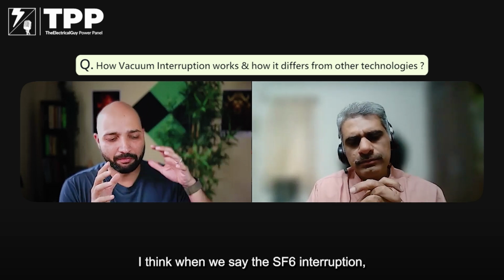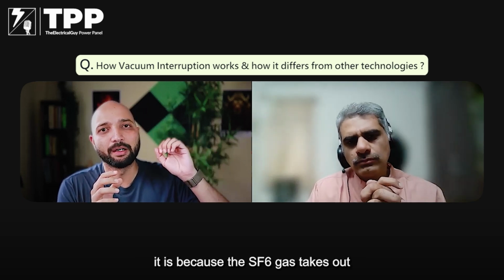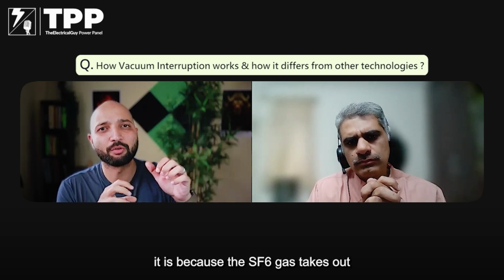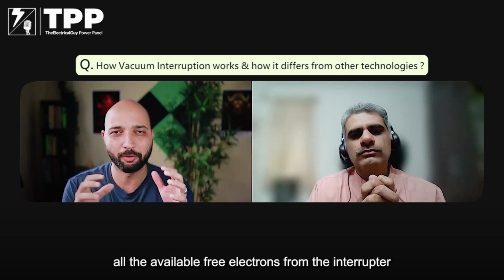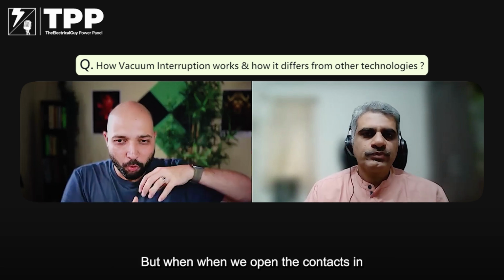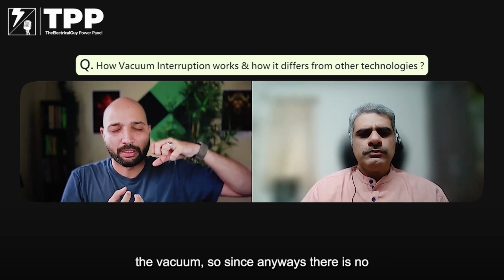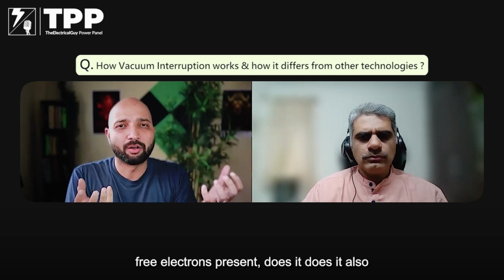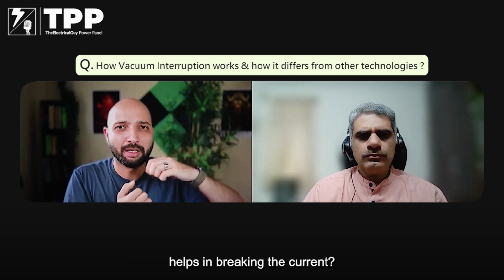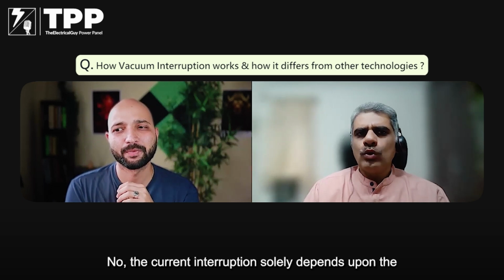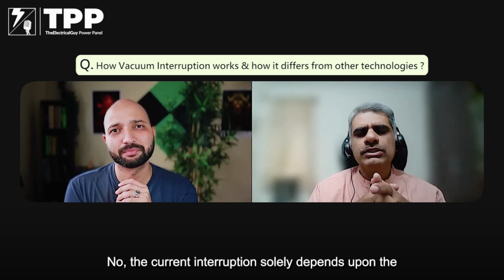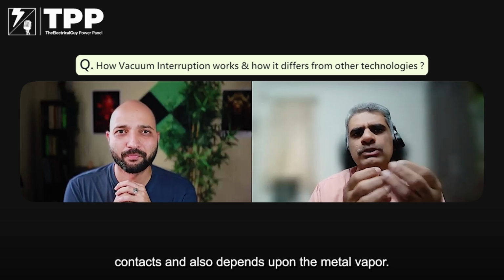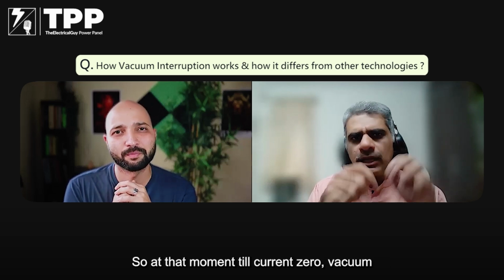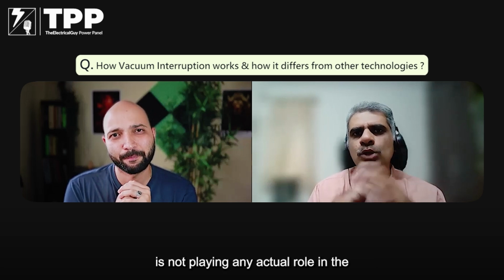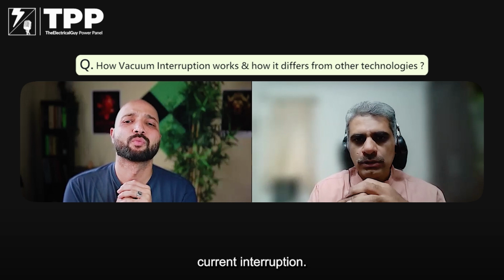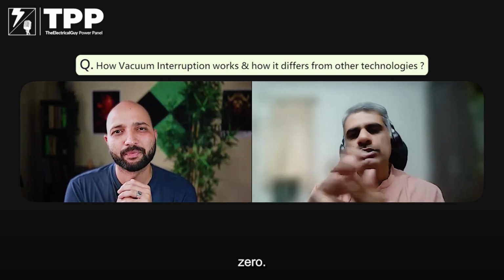Clear. I think when we say SF6 interruption, it is because the SF6 gas takes out all the available free electrons from the interrupter part. But when we open the contacts in the vacuum, since there are anyway no free electrons present, does it also help in breaking the current? No, the current interruption solely depends upon the contacts and also upon the metal vapor. So till current zero, vacuum is not playing any actual role in the current interruption. The role of vacuum starts only after current zero.